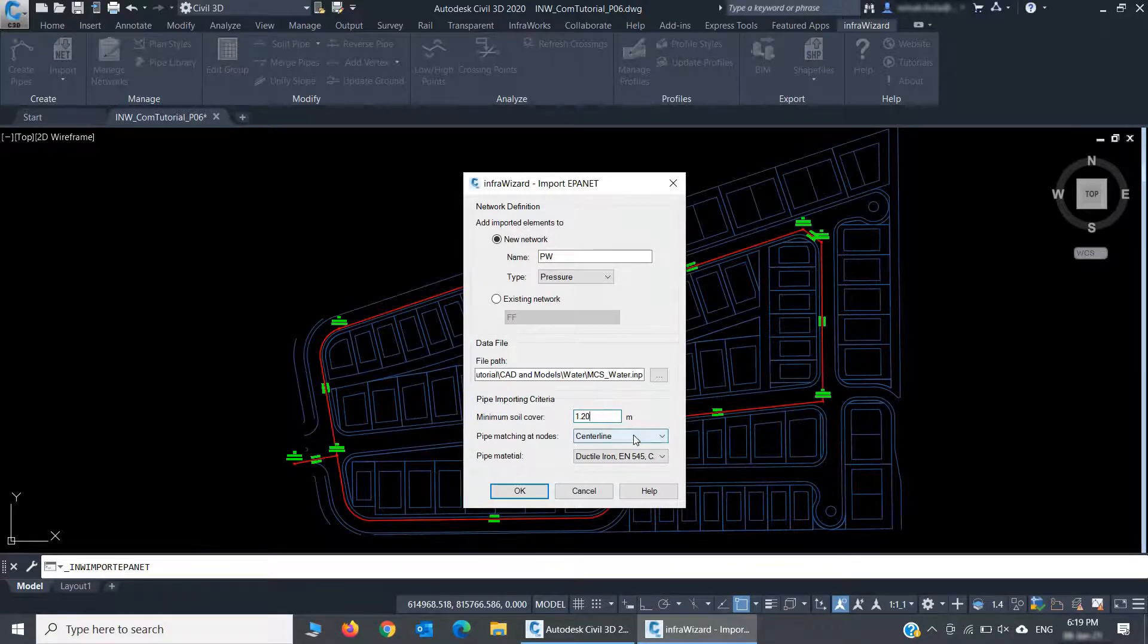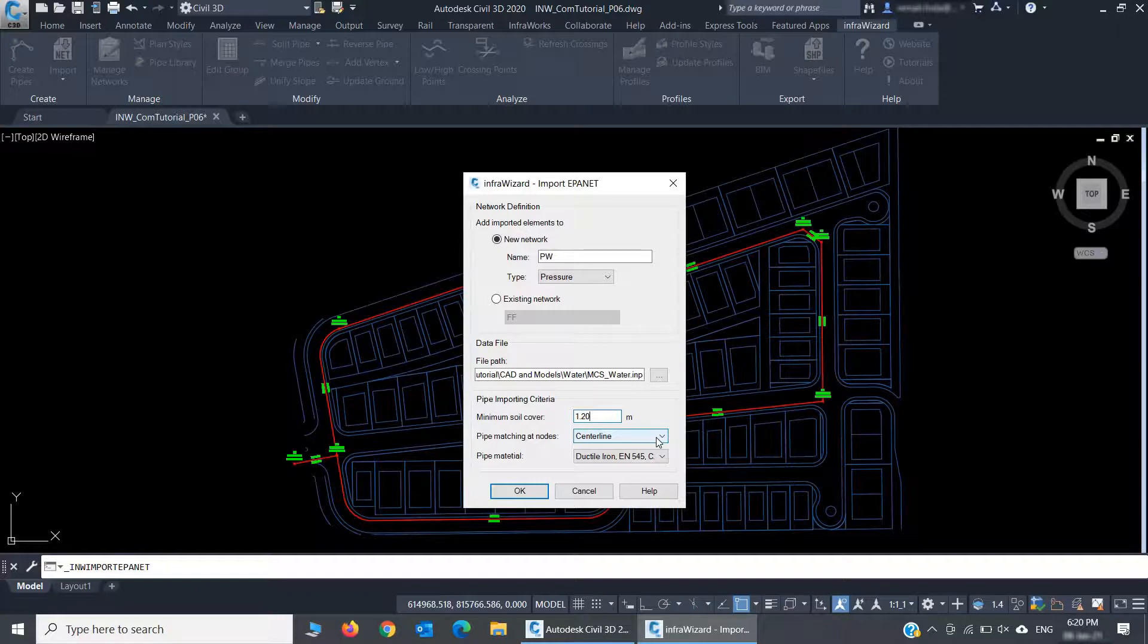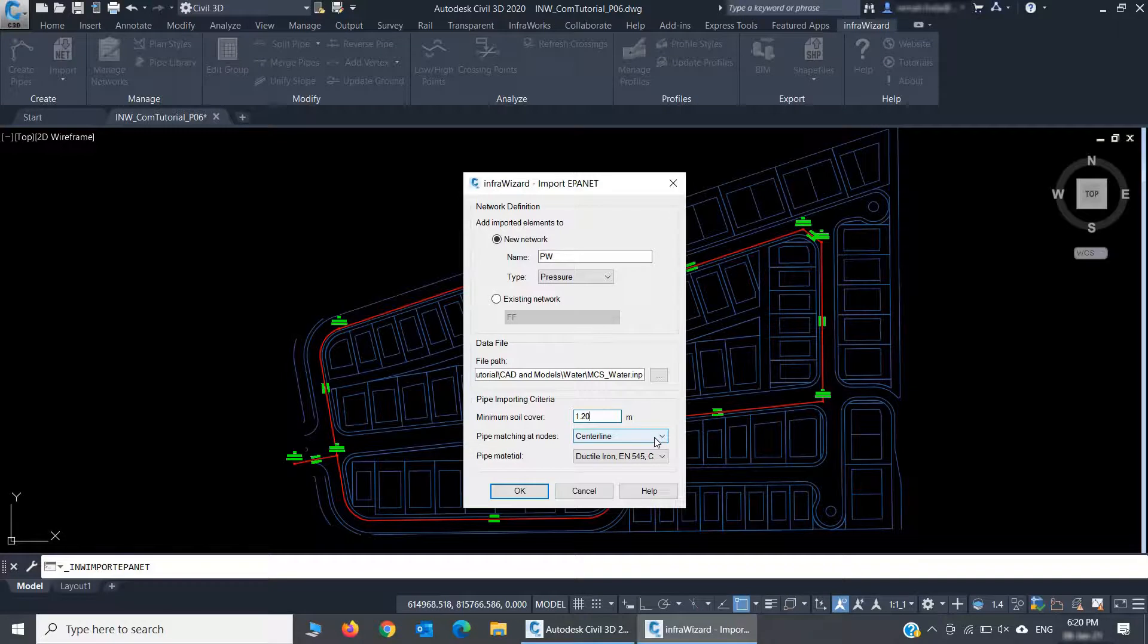The next setting is pipe matching at node. It's set by default to centerline, which means that the pipes of different diameters connected to one node will have the same center level at this node, which is also the common practice in pressurized water networks.